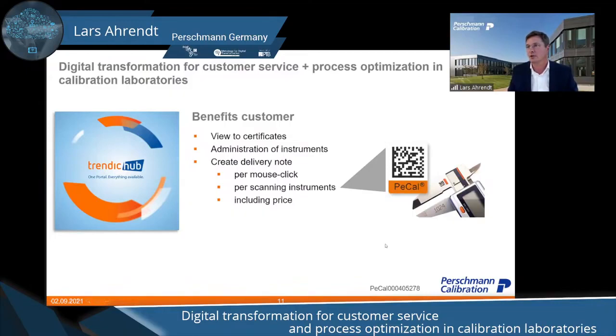If you scan that, you should see a number. The number of this is PECAL for our calibration laboratory, and then a number. This number is combined to the data set in our database. So each instrument has an ident number, of course, a visually inspected ident number, and our sticker, and our database connects this sticker with this ident number and the item itself. And if you scan this with our calibration software, then with this administration software, you see all information you are interested in.